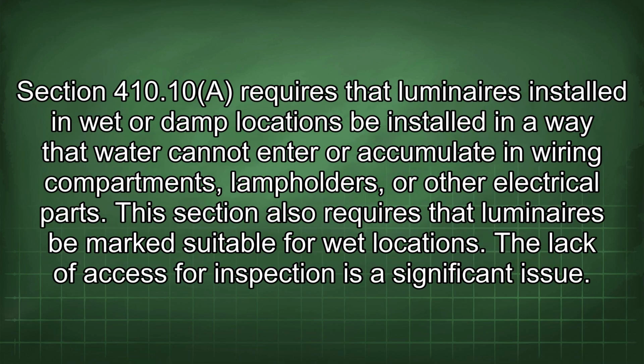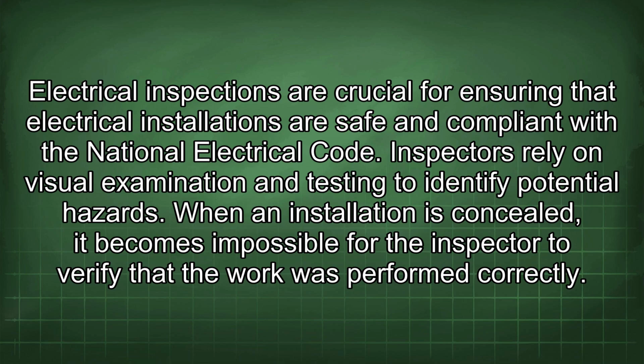Section 410.10 requires that luminaires installed in wet or damp locations be installed in a way that water cannot enter or accumulate in wiring compartments, lamp holders, or other electrical parts. This section also requires that luminaires be marked suitable for wet locations. The lack of access for inspection is a significant issue. Electrical inspections are crucial for ensuring that electrical installations are safe and compliant with the National Electrical Code.